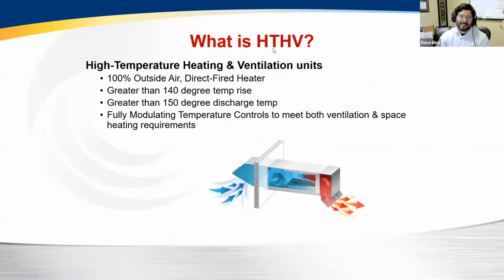Again, the technology we're talking about today is HTHV, or high temperature heating and ventilation. First and foremost, what is it? HTHV are direct fire industrial heaters that utilize outside air with a high temperature, meaning they have a greater than 150 degree discharge and a greater than 140 degree temp rise.